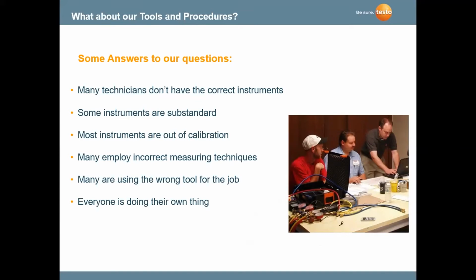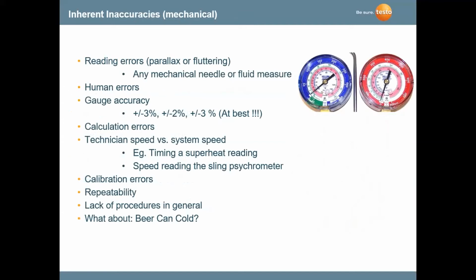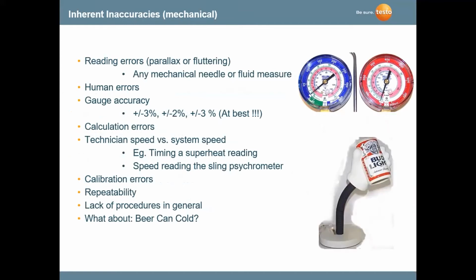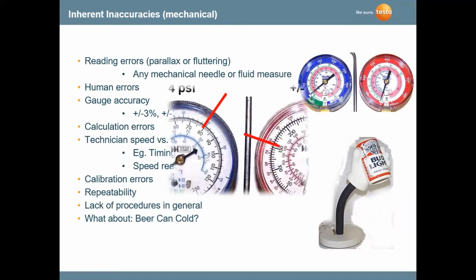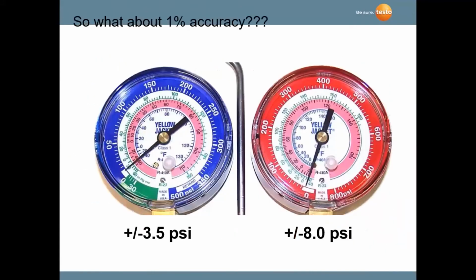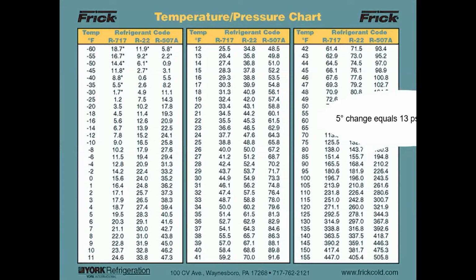What's happening and what's changing is that everyone in the past had a really inconsistent method of checking superheat and subcooling. What digital gauges have allowed us to do, and not only that, but the accuracies are much greater on digital instruments because of these reasons. Much greater than analog. Again, you have temperature differences, and you have some gauge inaccuracies, calibration errors, things of that nature. And these are just some of the calibration errors primarily that you're looking at on the pressure side of these analog gauges. Even our temperature charts are outdated a little bit, not so much outdated as much as they become inaccurate at certain sections of the temperature pressure chart.